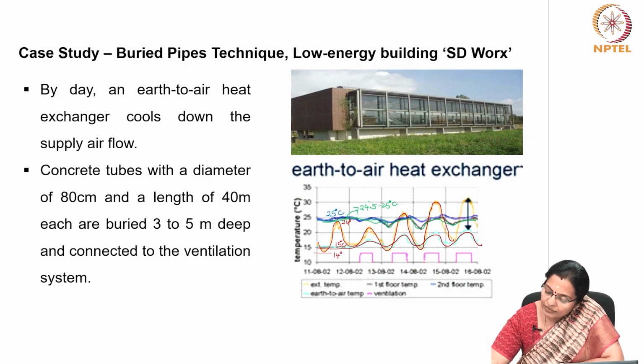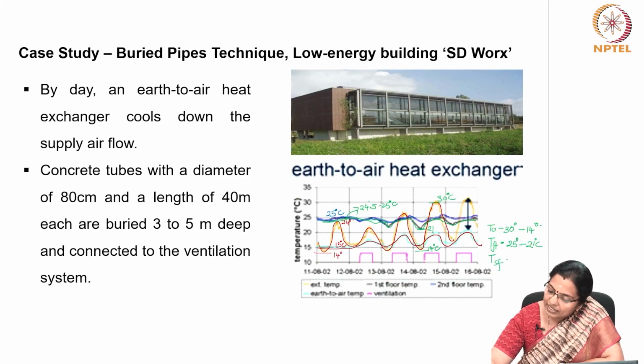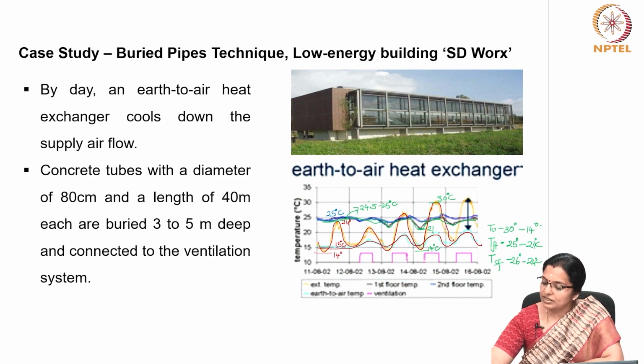On another random day, when the T outdoor is between 14 degrees centigrade to 30 degrees centigrade, so 30 degrees to 14 degrees, we can see the first floor temperature to be between 21 degrees and its maximum is 25 degrees. Whereas the second floor temperature minimum is 24 degrees and the maximum is about 26 degrees centigrade. So this is the impact the earth air tunnel or earth to air temperature has.